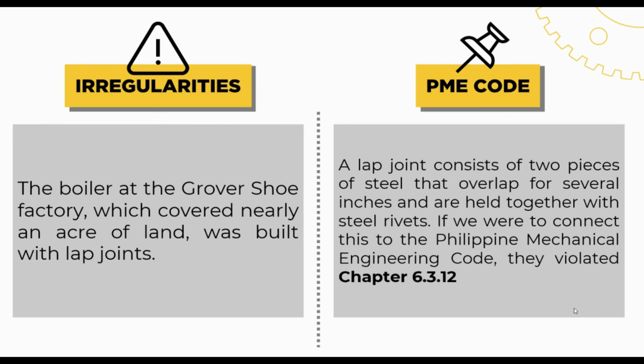A crack in the steel, perhaps imperceptible when constructed, had slowly widened under years of strain. As the boiler heated and cooled, the crack widened. Gradually, the steel weakened until it gave way in a massive explosion. Under the PME code, they violated Chapter 6.3.12, which covers the lap joint, and a lap joint consists of two pieces of steel that overlap for several inches and are held together with steel rivets.